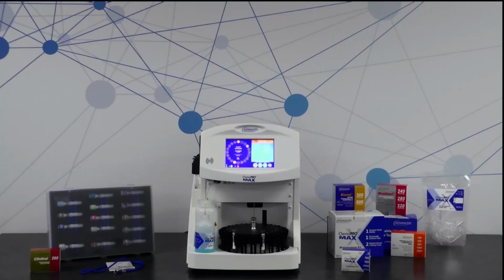Okay, is any calibration still required after 500 tests? Nope. As long as your QC is in and your temperature doesn't change significantly and you haven't moved the instrument anywhere, you're good to go. So we recommend a 6-month cycle. You can actually pre-program reminders into the software as well to say at the 6-month mark, hey, you should probably think about performing calibration, or even at the 12-month mark. But it's really only required when your QC calls for it. So as long as your QC is performing well, there's no need to calibrate. Okay, any additional calibration? Follow-up question there. So any additional calibrations besides QC failures?